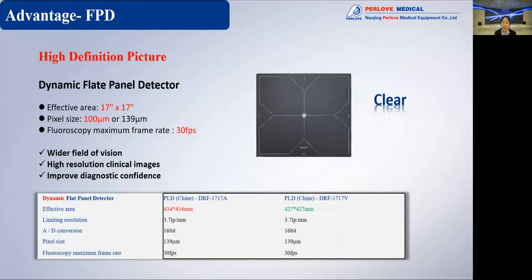For example, when one doctor observes one motion of the structure in three steps - first step, second step, third step - usually we observe the last step, right? But for the static flat panel detector, they usually give us the recording of the motion in the first step only. For the dynamic flat panel detector, it can record the observation of the motion from one to two to three. That is why dynamic flat panel detector can benefit fluoroscopy or motion observation very well.